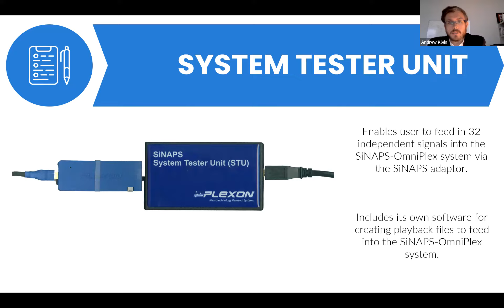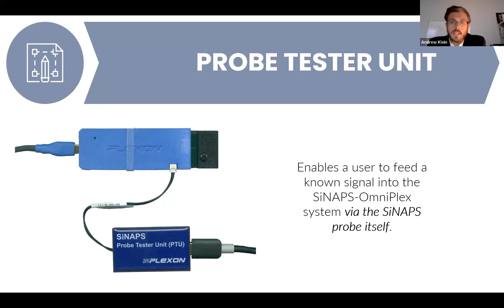For that, we have the probe tester unit. The probe tester unit is a device, a next generation device from Plexon and specific to the SiNAPS OmniPlex system. The probe tester unit will enable a user to feed a known signal into the SiNAPS OmniPlex system via the SiNAPS probe itself. The probe tester unit is a valuable device for testing and troubleshooting of the OmniPlex SiNAPS system.